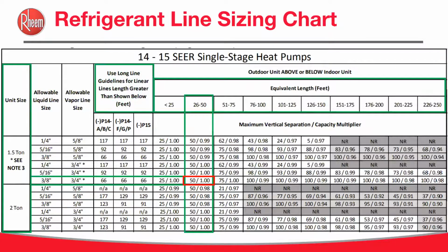So now let's look at what this means. We have used long line set guidelines for linear lengths greater than shown below. So what this means is if you're using 1/4 inch and 5/8 and you're running more than 117 feet, we're now going to have to follow long line set guidelines, which means you may have to add some extra stuff as per the manual in these cases.